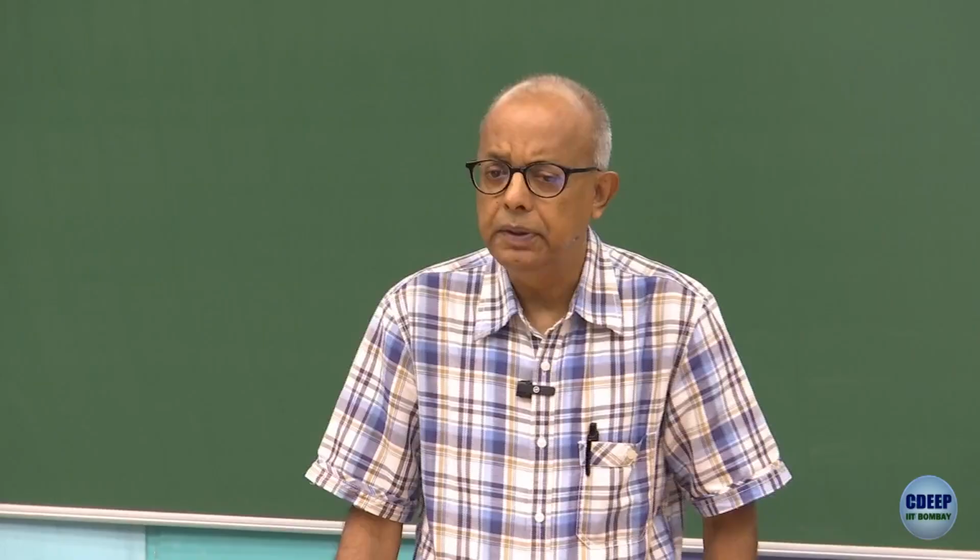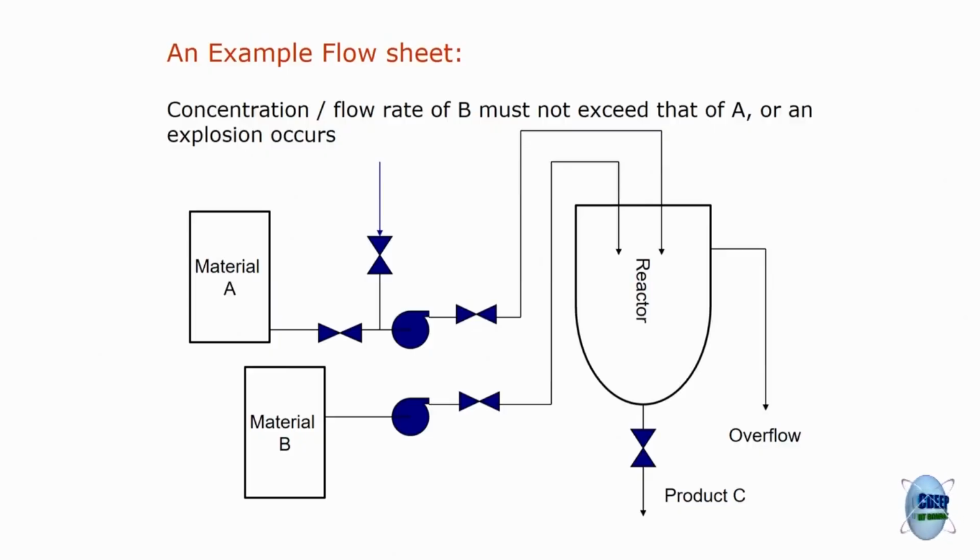Similarly for storage tank B. Now, if I move to the reactor, that is another equipment. What would be the design intention? You have to maintain a certain temperature, certain pressure, and certain level, because there is an overflow there. If there is excess material, it should overflow. That is the design. Temperature, pressure, what else? And the inlet concentration. Because when you design a reactor, how do you design? You use reaction kinetics to determine the volume, and thermodynamics to choose the temperature and pressure. What else is there where you can apply HAZOP in this setup?